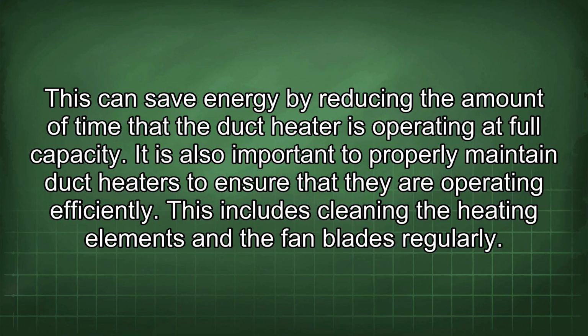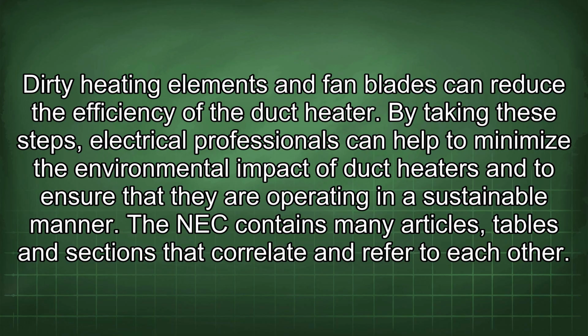capacity. It is also important to properly maintain duct heaters to ensure that they are operating efficiently. This includes cleaning the heating elements and the fan blades regularly. Dirty heating elements and fan blades can reduce the efficiency of the duct heater. By taking these steps, electrical professionals can help to minimize the environmental impact of duct heaters and to ensure that they are operating in a sustainable manner.